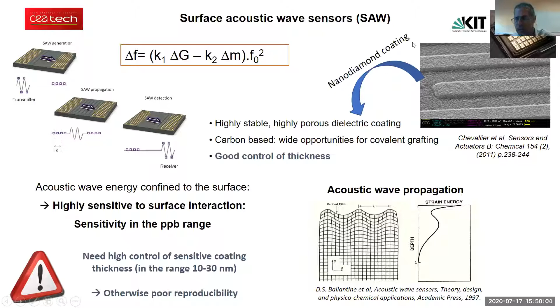This is why we developed this coating based on nanodiamond. We are depositing nanodiamond particles across the surface of our surface acoustic wave sensors. What you can see here are the gold IDT electrodes, and they have been conformably coated with these diamond nanoparticles. What we get at the end is a carbon surface, which is highly stable because it's diamond. It's nanoparticles, so we have a very high surface area, so we can make a very sensitive sensor. And we can also use this carbon surface to immobilize protein on the surface of these sensors. So this is what we did.